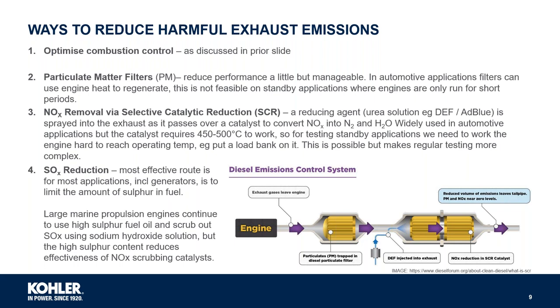Sulfur oxide reduction: the most effective route, including for generator engines, is to limit the amount of sulfur in the fuel. However, large marine propulsion engines continue to use high sulfur fuel and scrub it out using sodium hydroxide. But the high sulfur content does reduce the effectiveness of the NOx scrubbing catalysts.